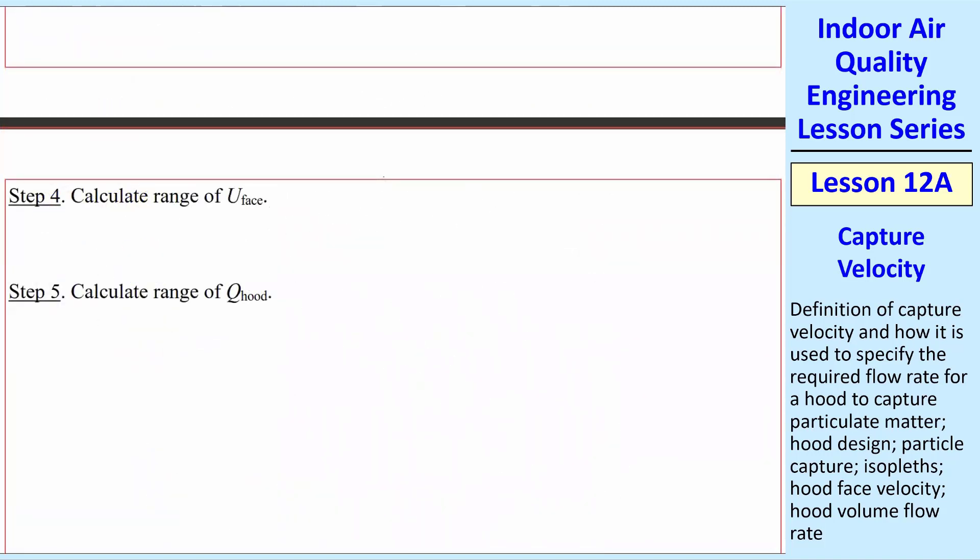Step four is calculate the range of Uface. U over Uface is equal to 0.075, from which Uface is U over 0.075, just solving for Uface. Uface is equal to 2,666.7 feet per minute.